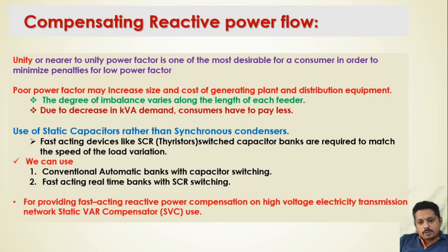For achieving reactive power compensation, we can have two different equipments: a conventional automatic bank with capacitor switching, and the latest technology, which is a fast acting real time bank with SCR switch. Actually, SCRs are very fast acting devices, and as we know, the load is continuously changing. Many industries' loads are not constant and they create reactive power very widely, and to compensate the reactive power in their area, we have to use these fast acting SCR switches.